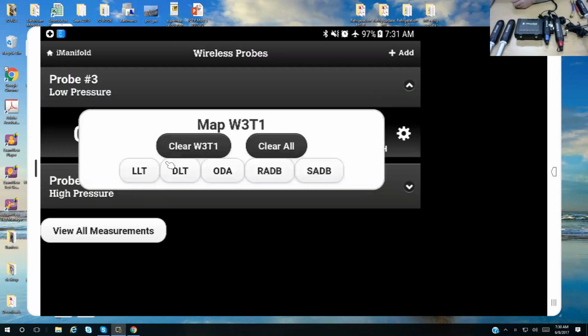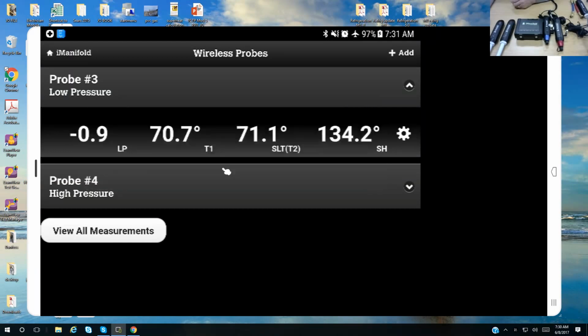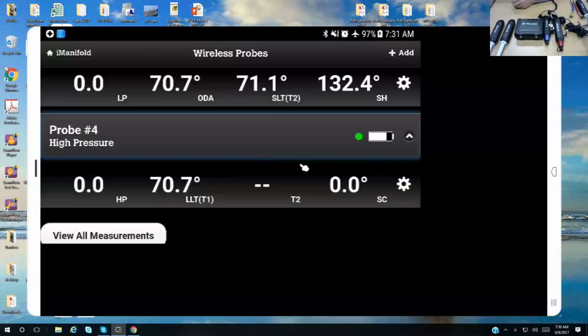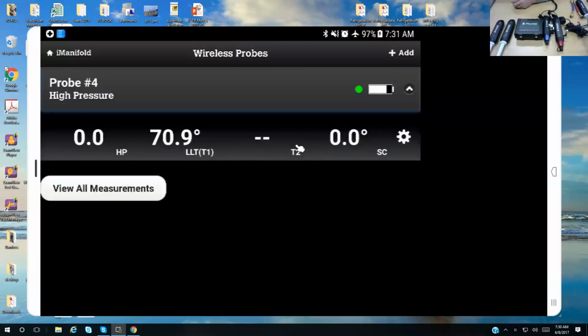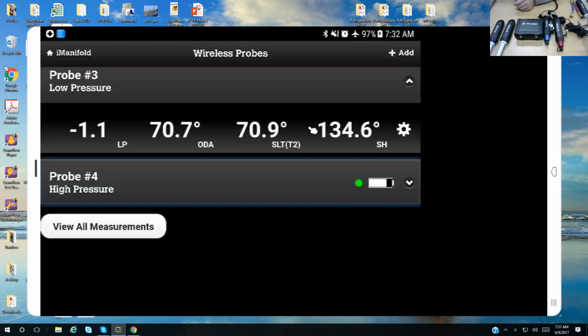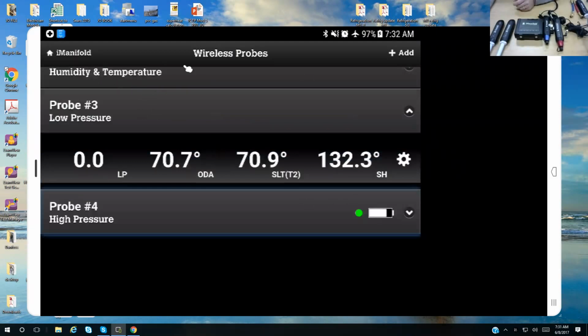And then I can just click on T1 here, and I want to have that be my liquid line temperature, discharge line temperature, outdoor air. Let's have that be the outdoor air. Again, on the high pressure probe, I don't have a thermometer here, but if I wanted to switch it over, once you get them configured and hooked up in the field and you realize, oh, I connected this one to the vapor line or this one to the liquid line, you don't have to disconnect and move the thermistors around. You can go back into the app and just remap it to wherever you had it connected in the first place. So now we have all 4 probes, the low and high pressure, supply and return for humidity 1 and 2. We have everything paired up.